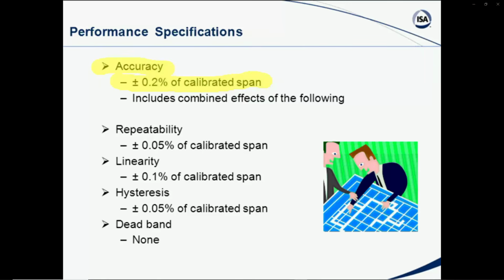And if we look at what the accuracy includes, first it has the repeatability. The repeatability is the ability of that transmitter to come back to the same output for repeating times for a specific input. In other words, if I put 50 inches of water on this differential pressure transmitter today, and I come back tomorrow and do it an hour later, I get the same output. Now the output may not be entirely correct, or may not be entirely accurate, but it will be repeatable.